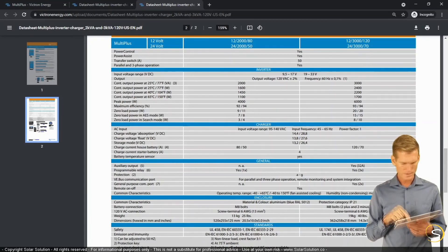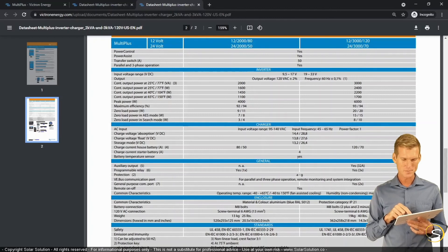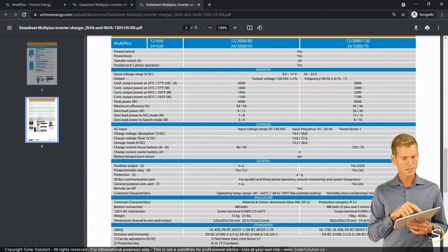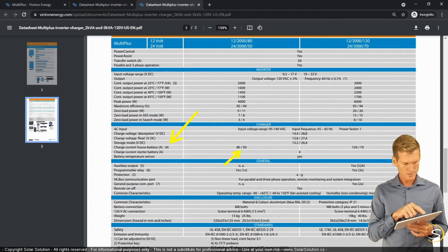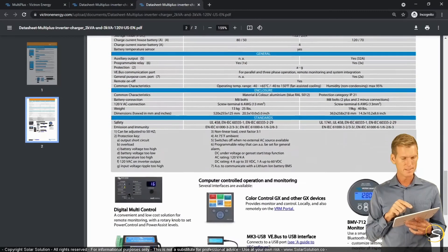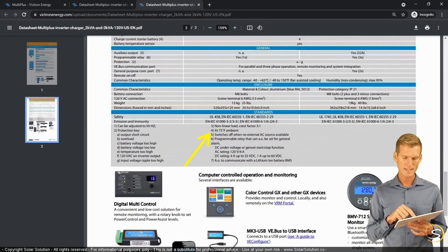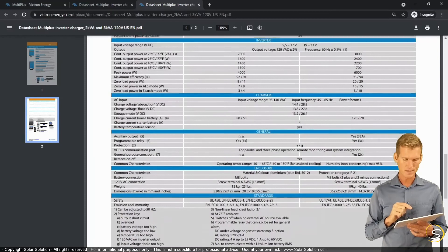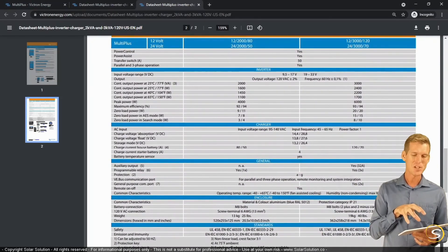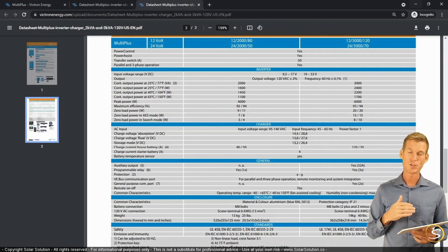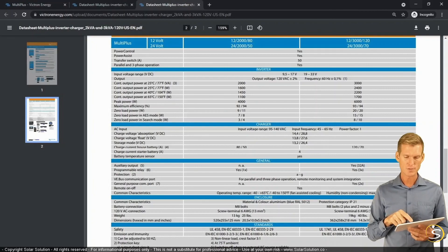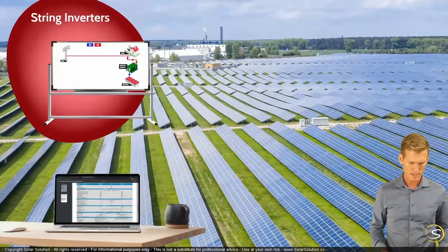I want to highlight a small note in the specification sheet because it can make a real difference in system operation. In the charger section, the charge current is listed as 80 or 50 amps, but note 4 states this is the charge current at 75°F ambient temperature — that's approximately 24°C. This probably means that at higher ambient temperatures the unit will charge more slowly, which is typically how these chargers work. So that was a real-life example of an inverter-charger and its specifications.